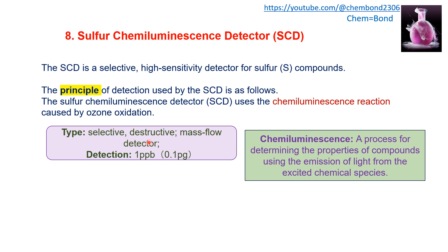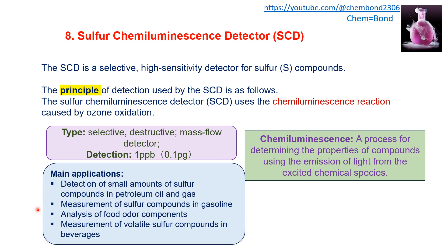The SCD is a selective destructive mass flow detector. Detection limit is 1 ppb or 0.1 picogram. Applications include detection of small amounts of sulfur compounds in petroleum, oil, gas, and gasoline, food odor compounds, and the analysis of volatile sulfur compounds in beverages.